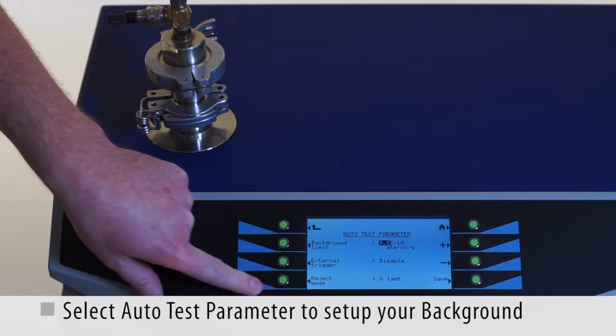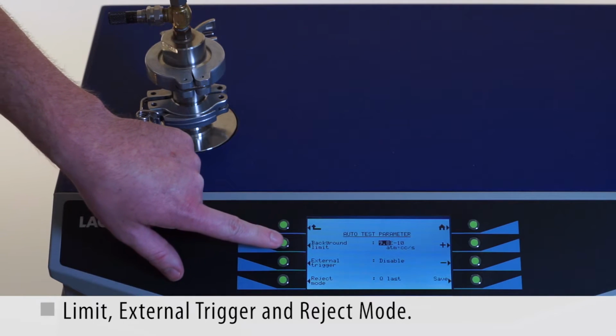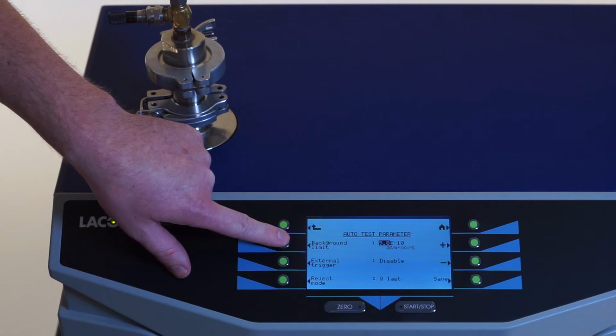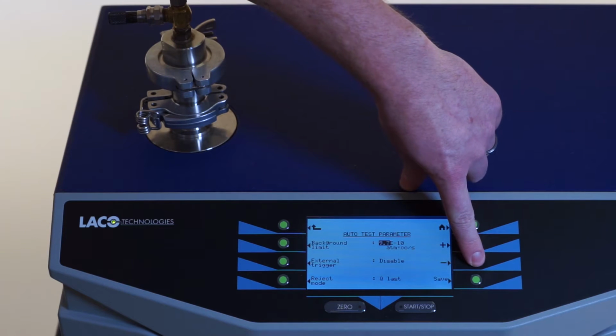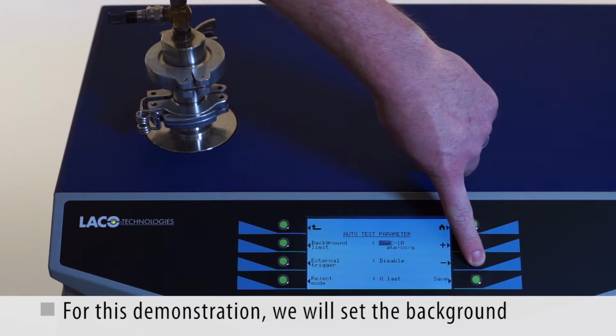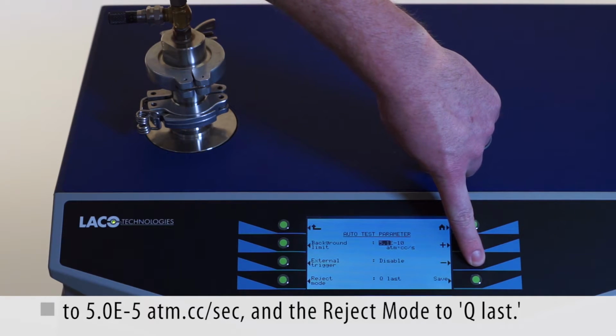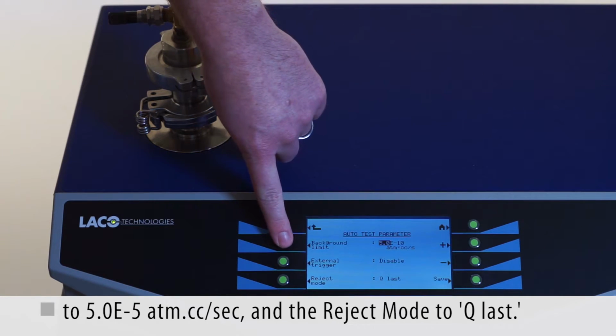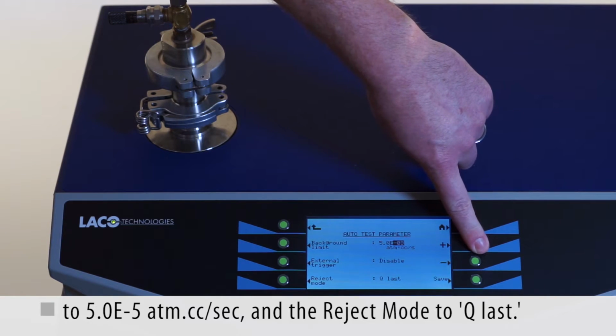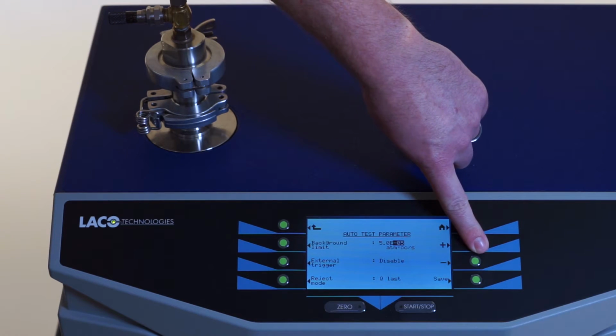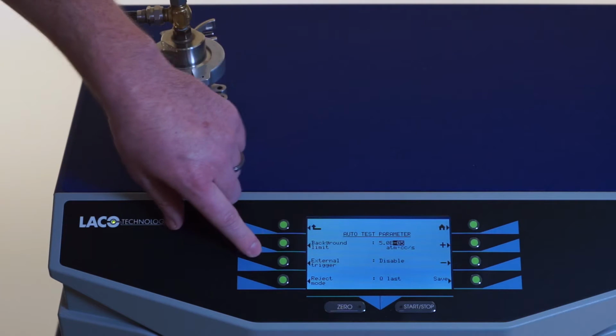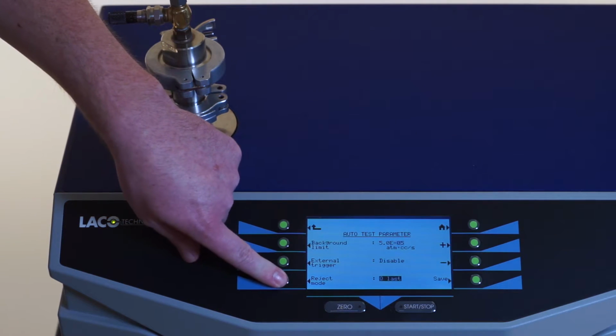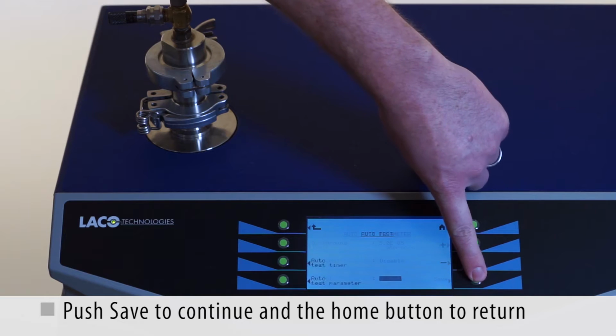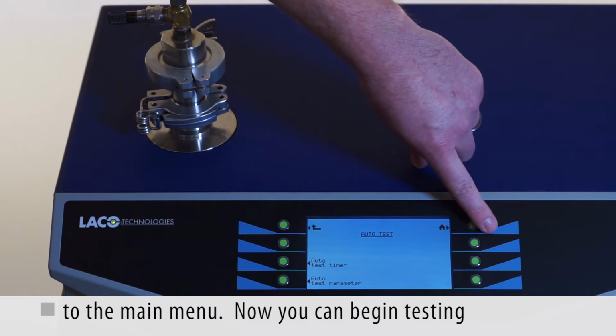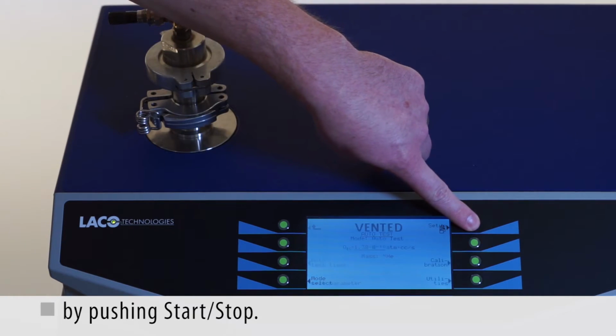Select Auto Test Parameter to set up your background limit, external trigger, and reject mode. For this demonstration, we will set the background to 5 to the -5 atmosphere cubic centimeters per second and the reject mode to Q last. Push Save to continue and the Home button to return to the main menu. Now you can begin testing by pushing Start or Stop.